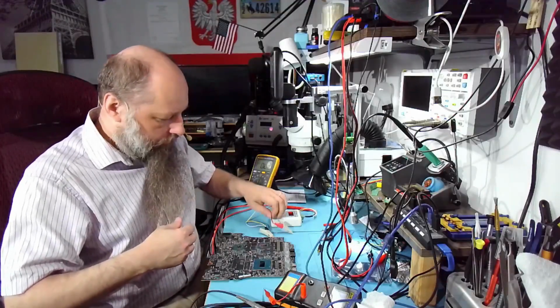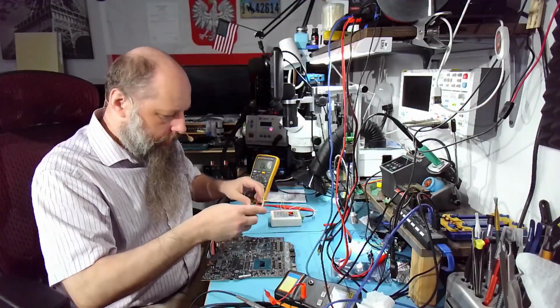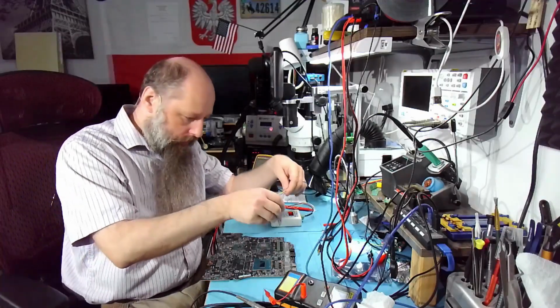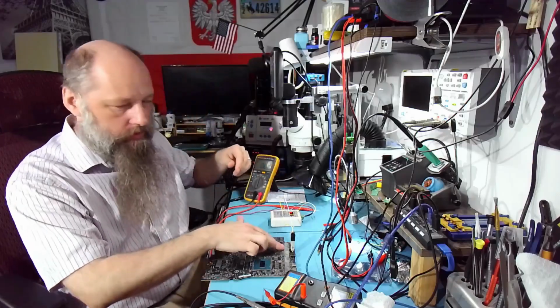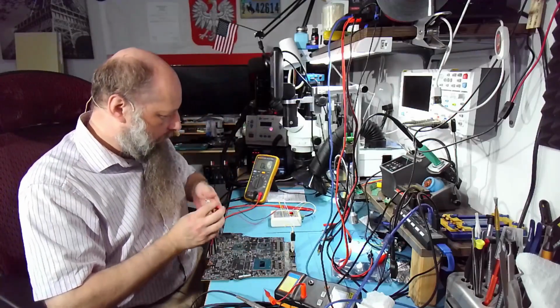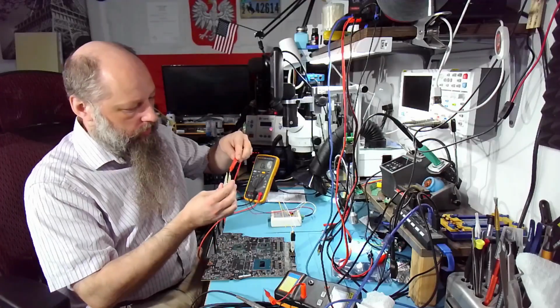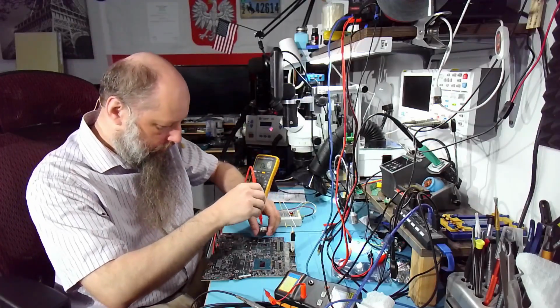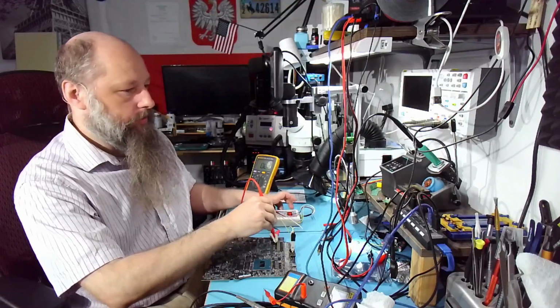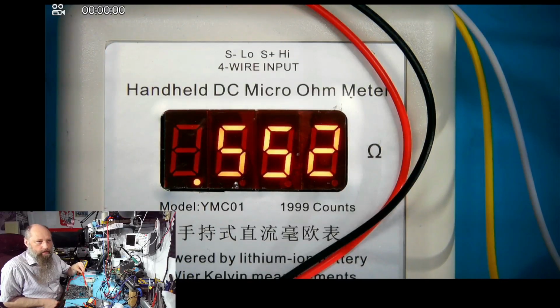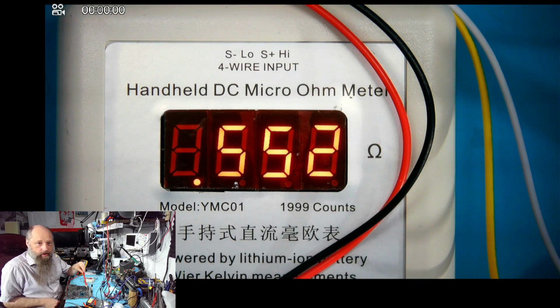So now let's measure the actual GPU between the ground and the coil. So what we can do, we can just clip it on one of the ports to catch the ground. Then what I do is I use my very good probe. I clip it like this and I touch the coil. And now remember that our meter showed 1 ohm, around 1 ohm. It's actually 550 milliohms, which is correct. For this GPU, 500 milliohms is fine. This reading can go as low as maybe 120, 150 milliohms, but anything lower than that is suspicious.